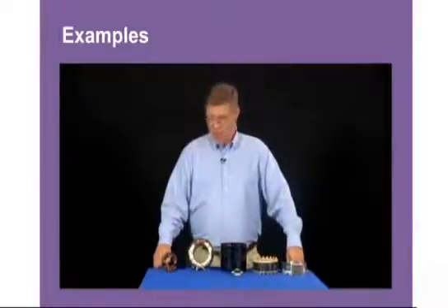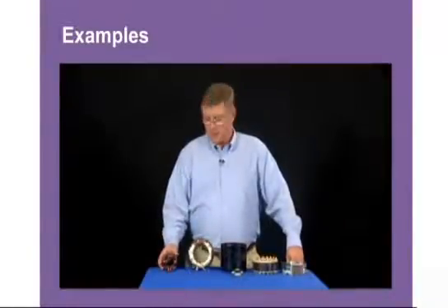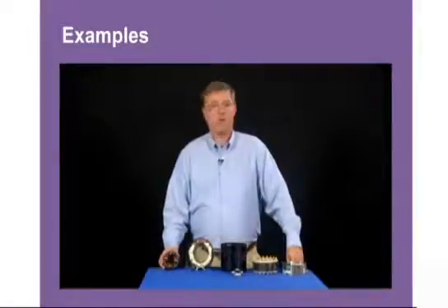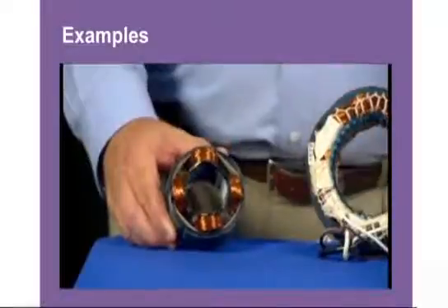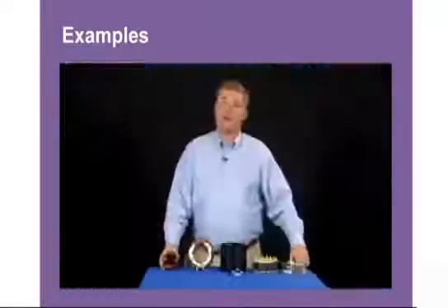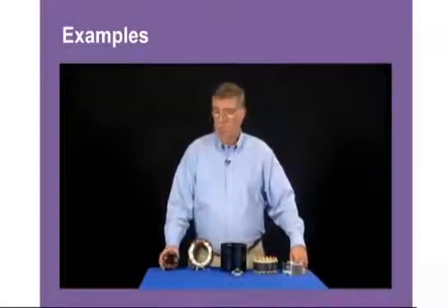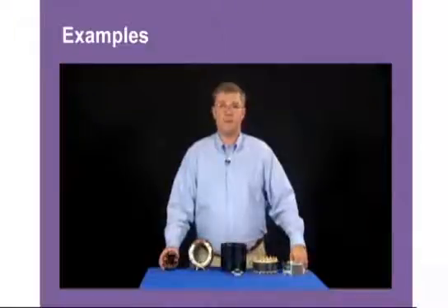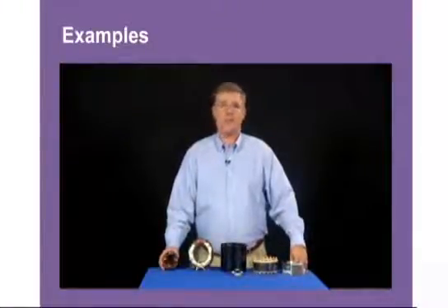The first type is a shaded pole motor. This motor has one distinct coil or run winding, and there are shading bands or copper bands that are forced through the stator that help fix the rotation. This is the least efficient motor in the HVACR market — a shaded pole motor is between 30 and 35 percent efficient.